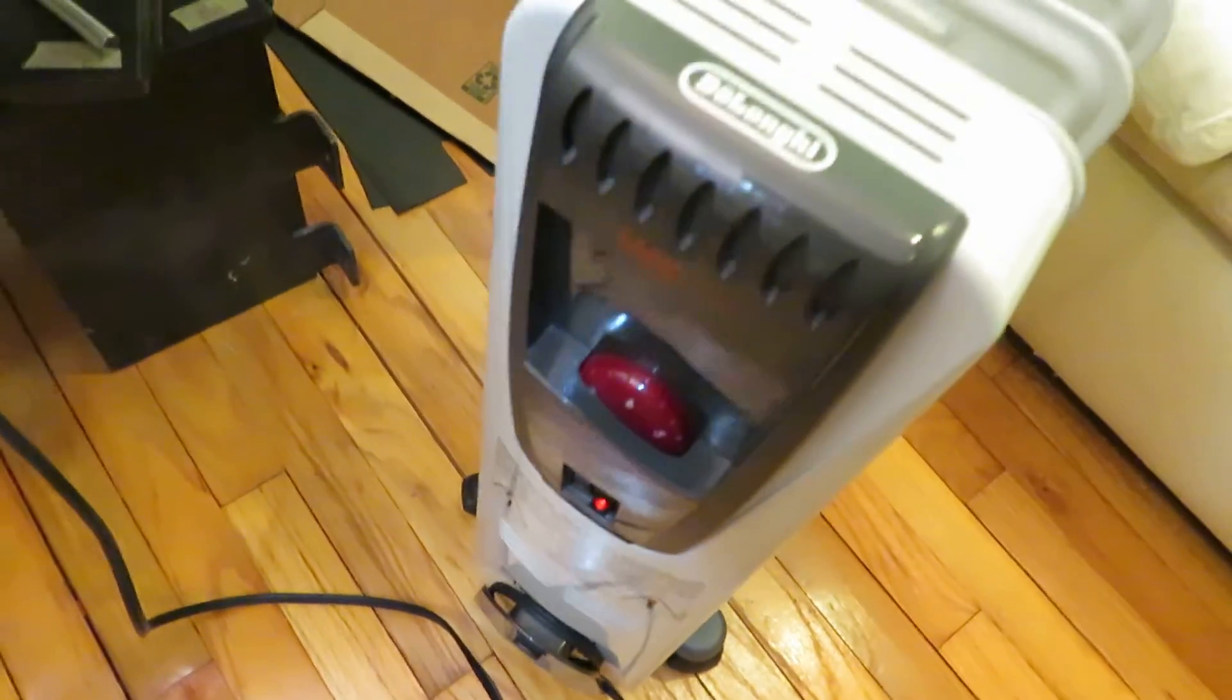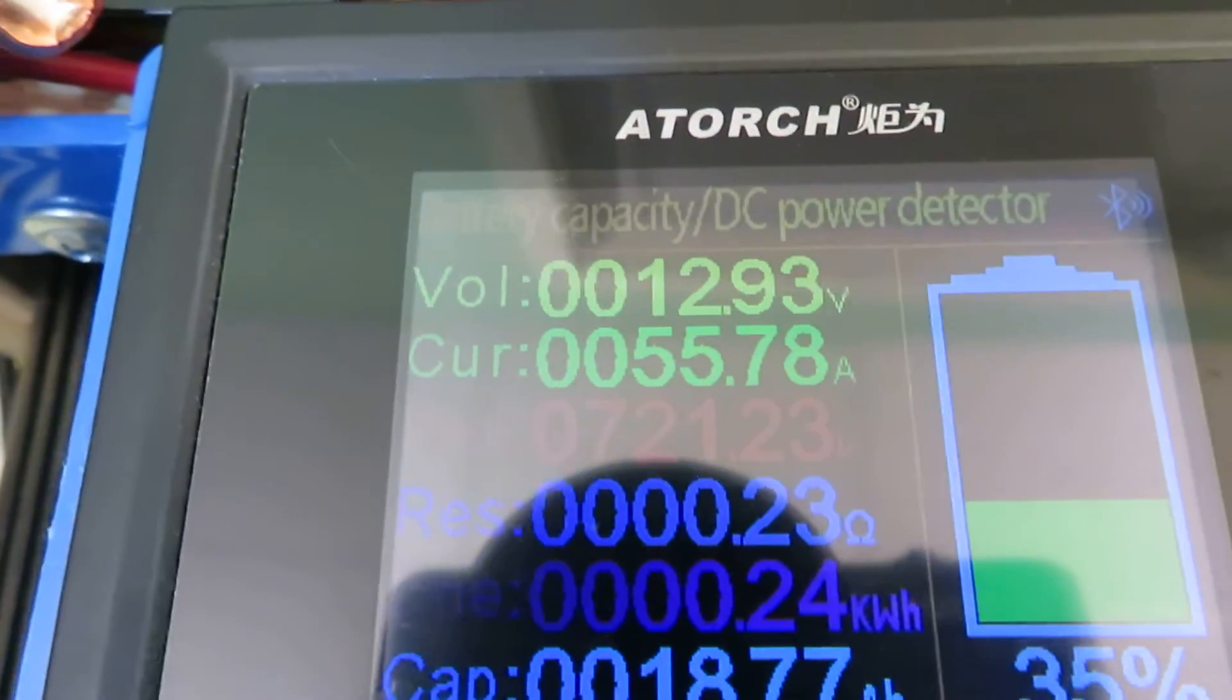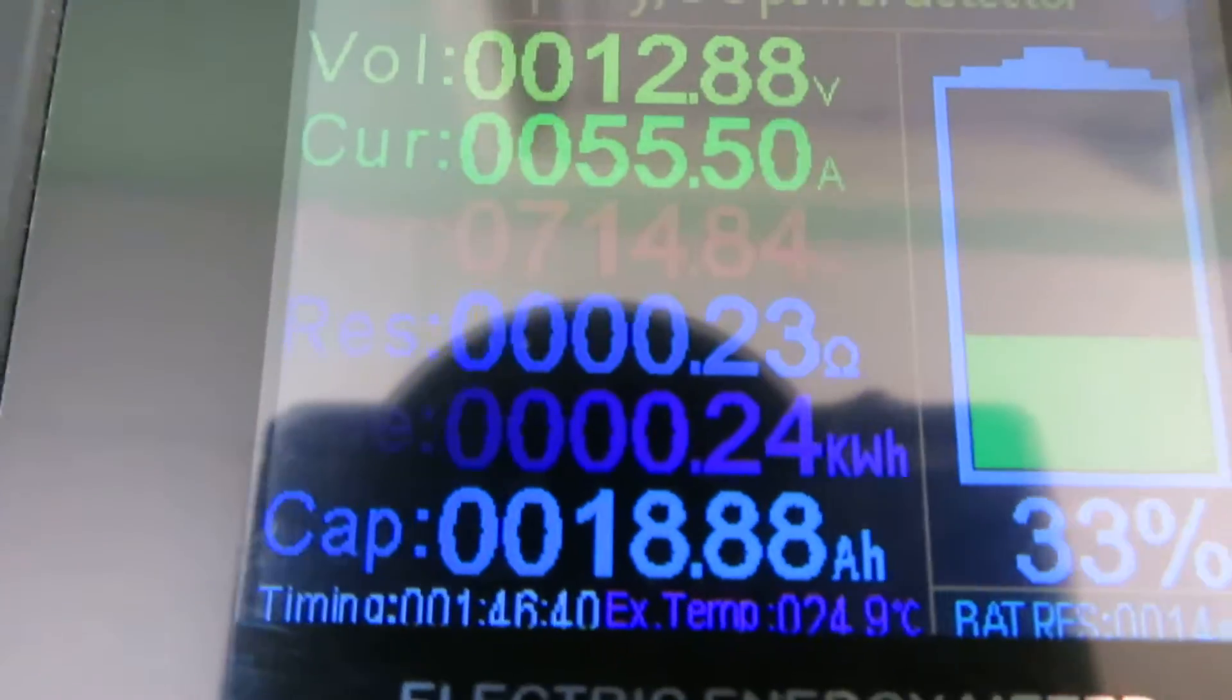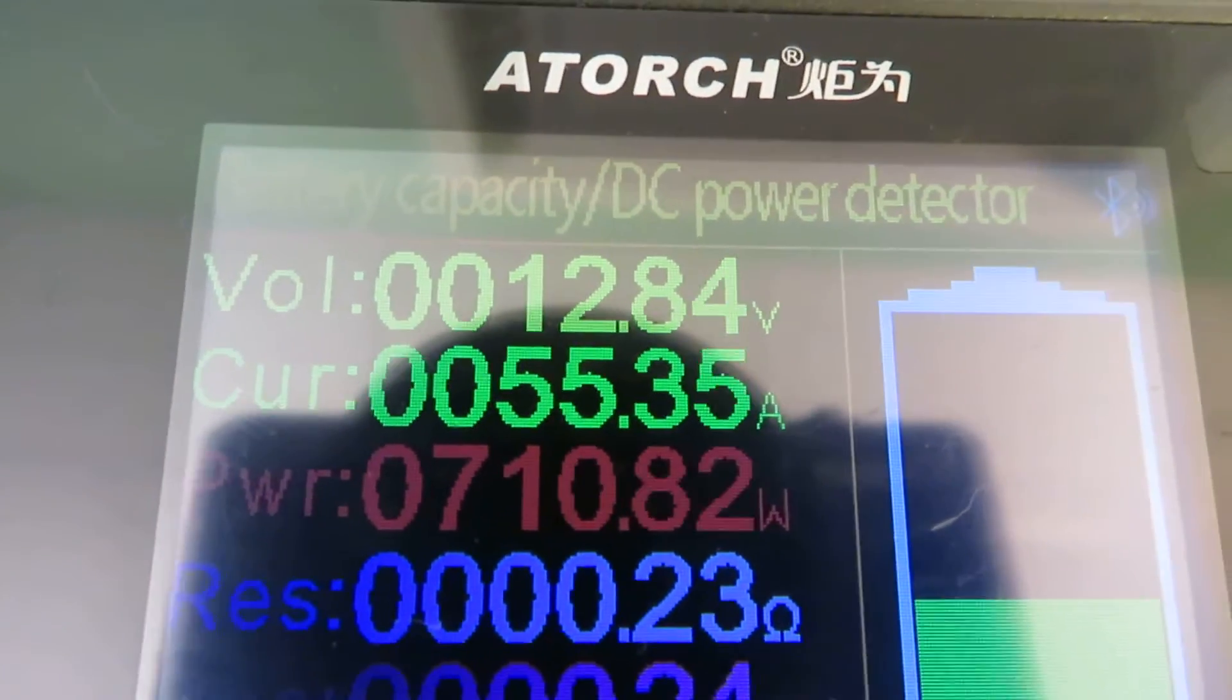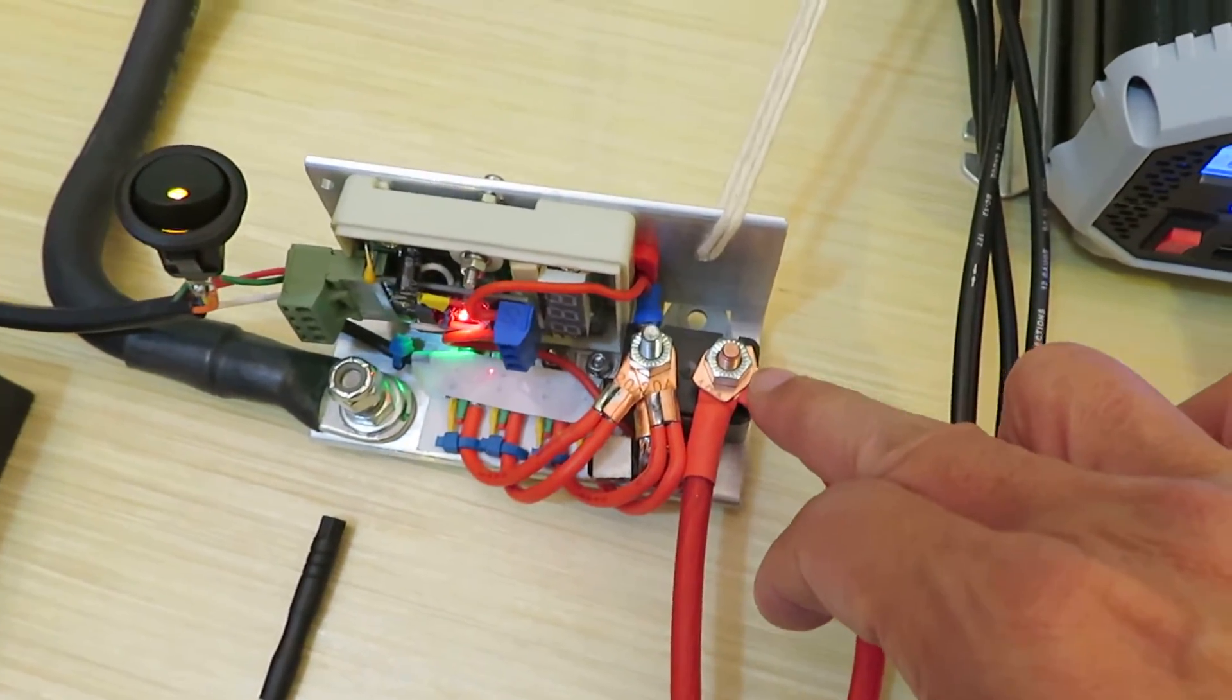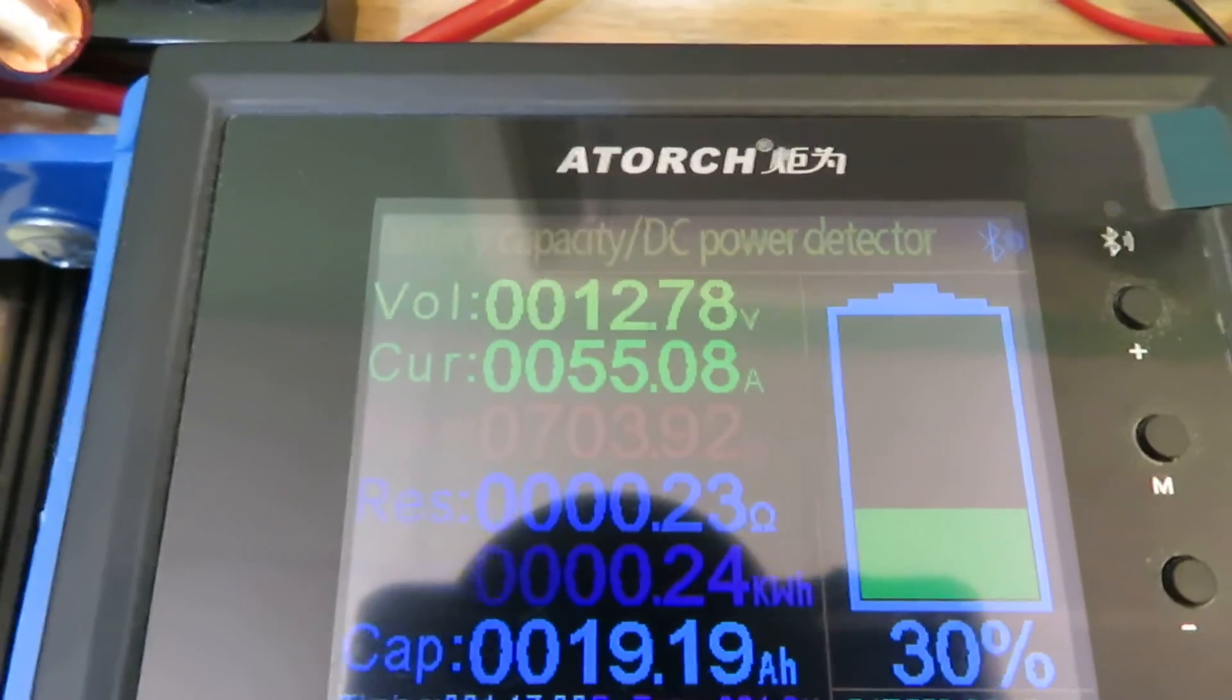So the heater comes on and the current is now 55.7 amps. And the wattage is about 700 watts, 711 watts. So even though the circuit breaker is only for 50 amps, and now it's drawing higher than 50 amps, it's 55 amps.